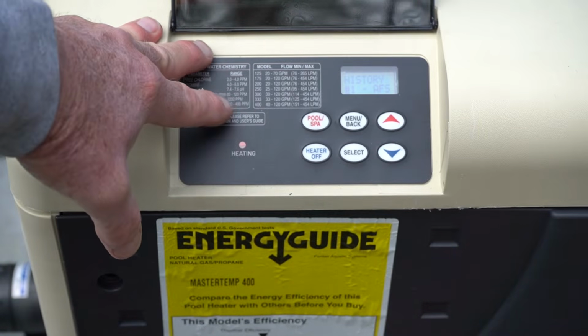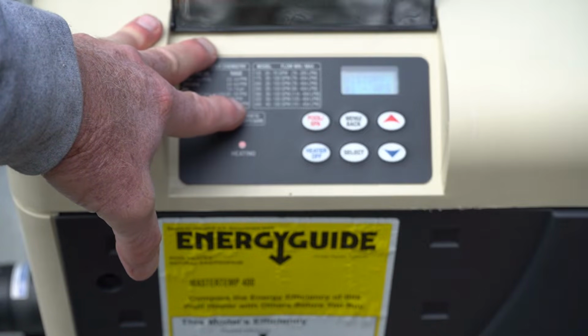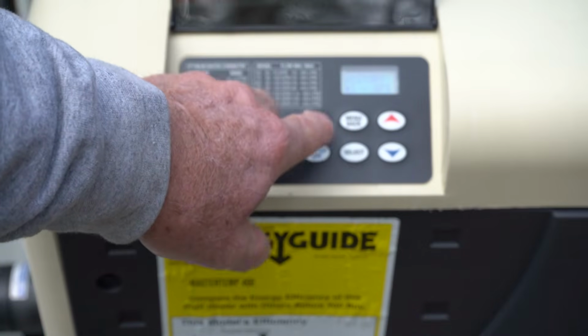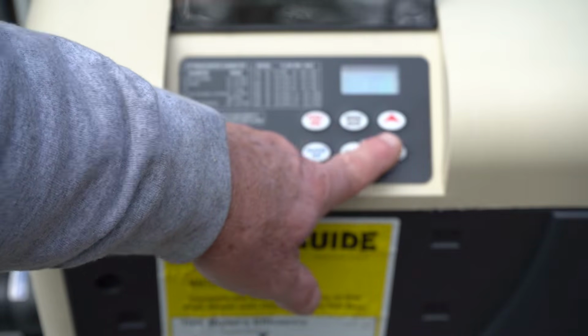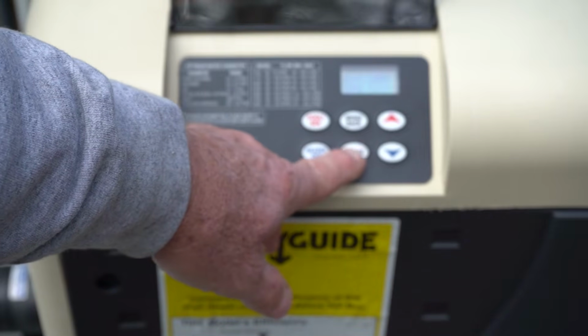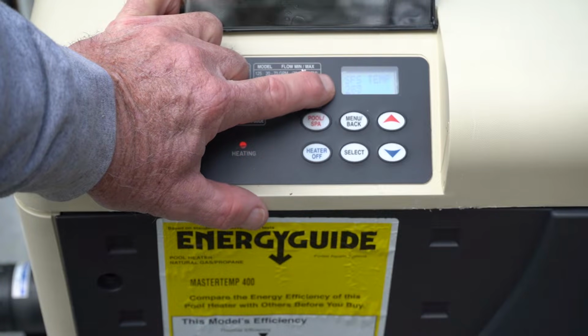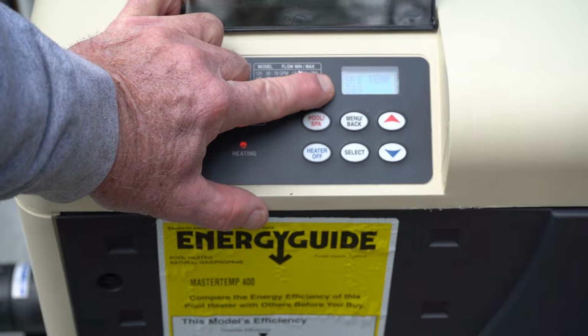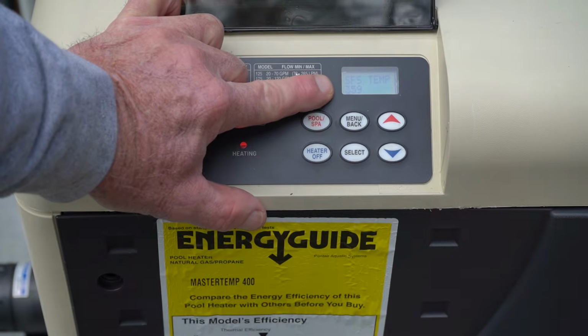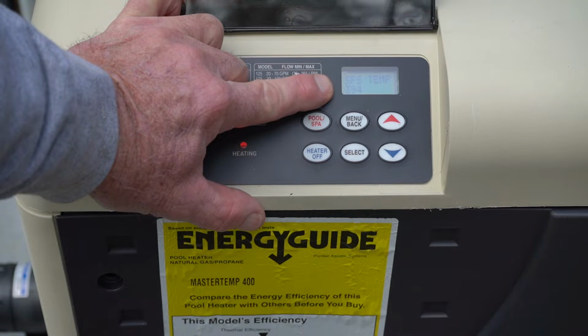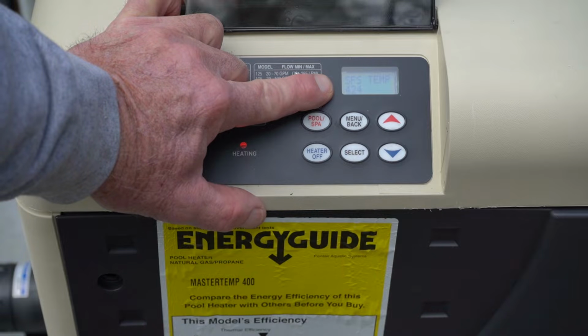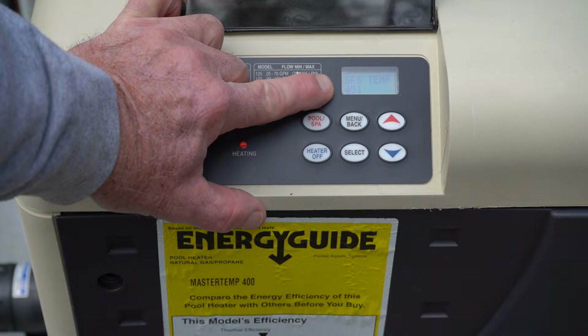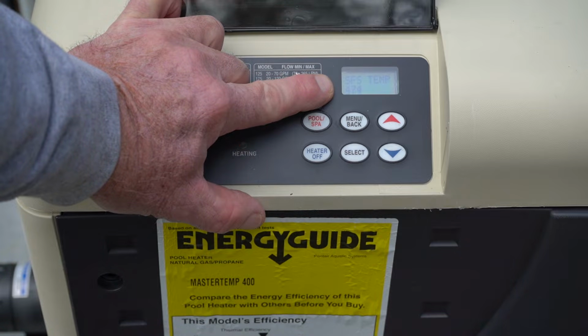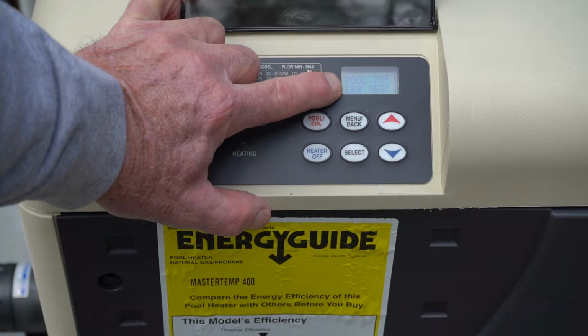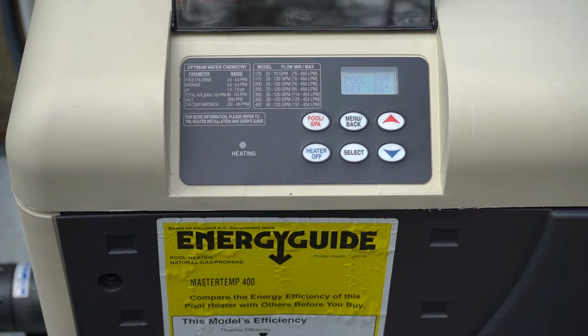Well, the airflow sensor, as you saw when I first turned it on, comes on and it says, oh, okay, well, it's failed, until the fan kicks in and it actually causes the heater to come back on. So now we're going to go back and we're going to go down to where it says stack flue sensor, and we're going to select that. And you can see that it's climbing rather quickly. We're already at 300 degrees, and when we get to 480 degrees, then that will trip out this heater, because of course the stack flue temperature is too high. So we're 450, 460, 470, and there you go, 480 degrees, and you can see that it says error SFS, which stands for the stack flue sensor.